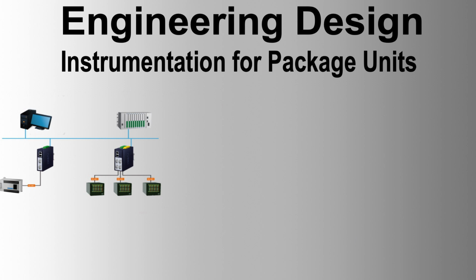Control and IPF SIF. General. Control and IPF for the equipment package shall be implemented in separate systems unless allowed by IPF SIL determination. In any case, the principal's approval shall be obtained if control and IPF SIF functions are to be implemented together in one system. Control. Control equipment, CPU, power supply units, and internal communication buses shall be redundant. Control input cards and control output cards shall be redundant unless single-loop integrity is implemented.